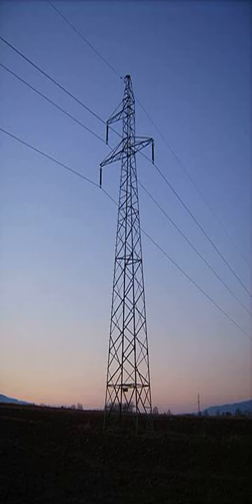High-voltage direct current transmission lines are either monopolar or bipolar systems. With bipolar systems, a conductor arrangement with one conductor on each side of the tower is used. On some schemes, the ground conductor is used as electrode line or ground return. In this case, it had to be installed with insulators equipped with surge arresters on the pylons in order to prevent electrochemical corrosion of the pylons.